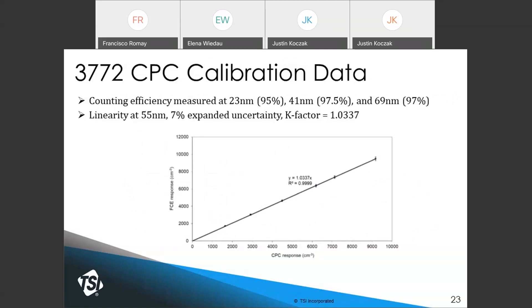A linearity curve for the 3772 reference CPC, similar to that for EE CPCs, shows a gain factor of 1.03 measured with 55-nanometer particles. Counting efficiency is also measured; for this particular CPC, 95% count efficiency was achieved at 23 nanometers, meeting the requirements for a reference CPC.